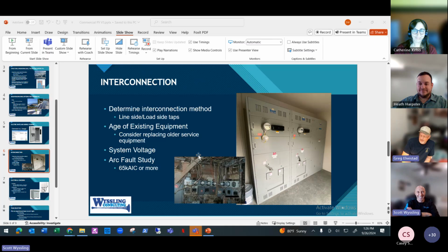Interconnection. How can we plug this stuff in? We can do a great job of designing a system, but if we can't plug it in, it doesn't do us any good. It doesn't do the client any good. A couple of examples of old stuff and not so old stuff, but the key point here is, what's the best way to interconnect? We have two options, of course, line side and load side. For commercial properties, where you connect is crucial. You have to have a full, accurate survey, clear photographs done with safety personnel on site to properly expose the busing and switchgear, switchboards, what have you, to assess where a connection can be made.